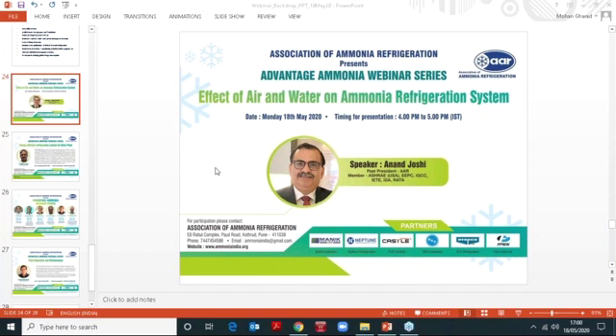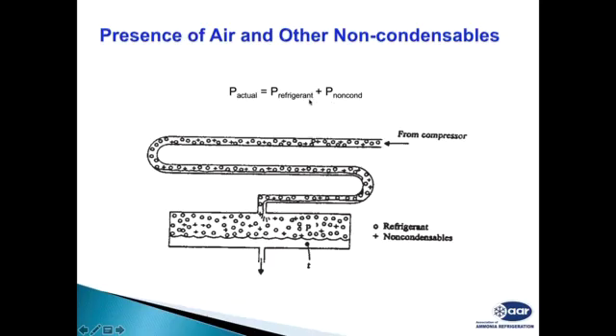This difference, and this formula which I'm showing you, is the actual pressure versus the refrigerant pressure. What is higher than the refrigerant pressure is non-condensable. The actual pressure is measured at the gauge on the receiver, and you measure the temperature of the liquid and convert that temperature into the saturated pressure, which is the refrigerant pressure. So the difference is non-condensable gases.